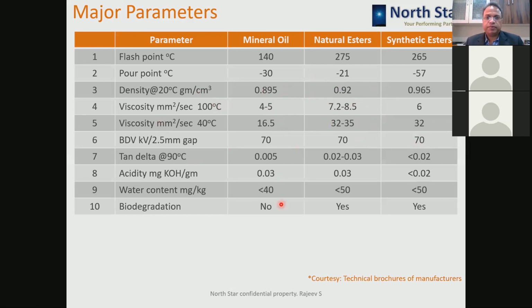Tan delta values: for mineral oil it is least, 0.005 at 90 degrees centigrade. For natural esters, it is 0.02 to 0.03 in that range. And for synthetic ester, it is highest, that is 0.02. Normally a question comes that when synthetic or natural esters are used, the tan delta is very high, so it means it is not a good insulation. But that is not to be understood like that, because mineral oil per se has the property of low tan delta, that is 0.005, and synthetic and natural esters by nature have high tan delta. So that is not a negative. If we compare mineral oil and natural esters for these properties, then we are comparing oranges and apples, which is not a wise comparison.